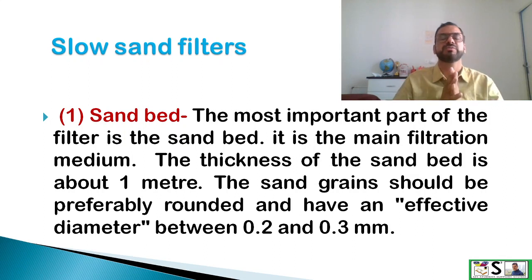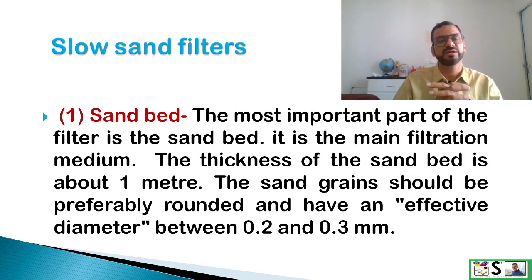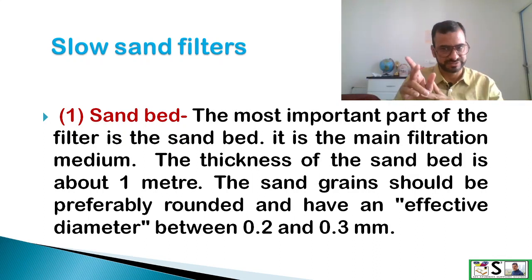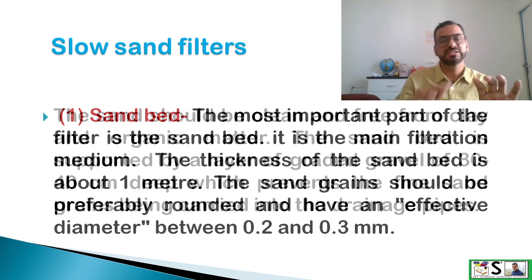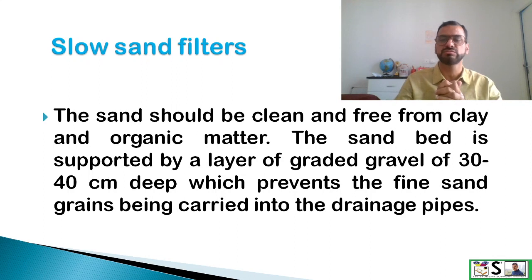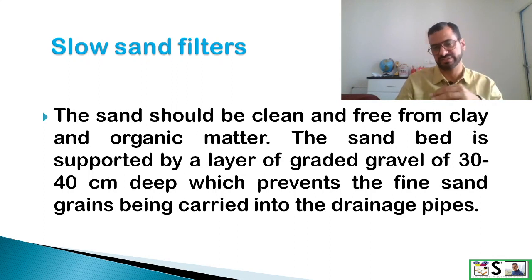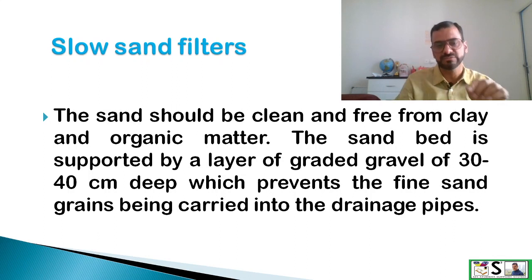The most important part of any filter is the sand bed, which is the same in both rapid and slow sand filters. The upper layer is fine sand of approximately 1 meter depth. The sand grains should be perfectly round with an effective diameter of 0.2 to 0.3 mm. This sand bed is supported by graded gravel of 30 to 40 cm depth, which prevents fine sand from being carried into the drainage pipes.